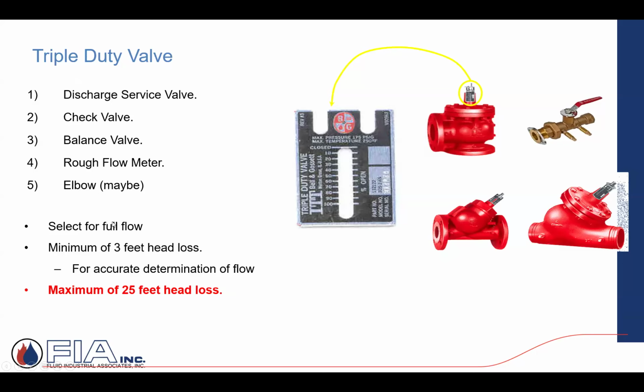When you select them, and you're looking at that suction diffuser and, in this case, the triple duty valve, you're looking for full flow. What's the design flow rate that you're going to be using with this pump and this system? Make sure that this triple duty valve is sized for it. Make sure when you're selecting it that it has a minimum of 3 feet of head loss. On the high side, the maximum, ideally don't select it for higher than around 25 feet. But we want to have some pressure drop so that we can actually use it for accurate, or fairly accurate, flow determination.